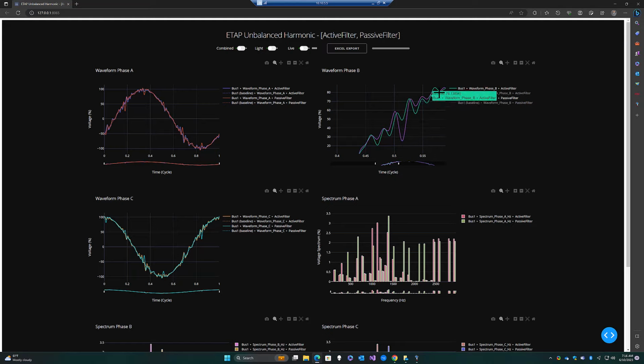So of course the purple line shows a bit more distortion than the green line, but the true test comes in when we compare the spectrum itself. And you can see that the active filter reduces the distortion significantly on the lower orders, which is what we want. And the passive filter is not able to achieve that on either the lower orders or the higher orders in this case. So obviously not a fair comparison, but at least a comparison to give you an indication why active filtering is used to adapt to the electrical system versus a fixed tuned passive filter.